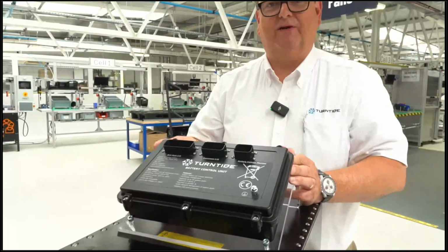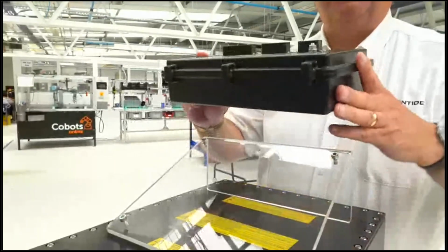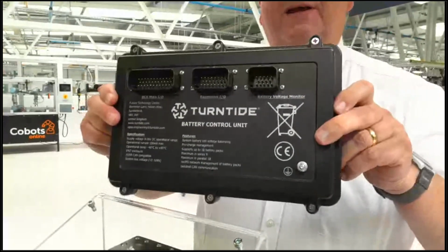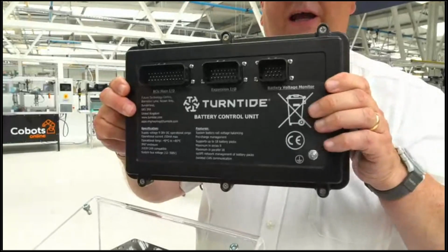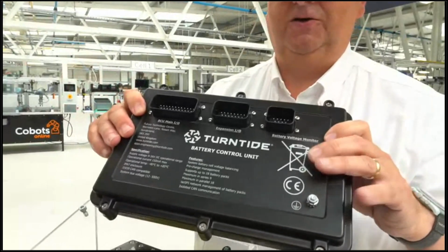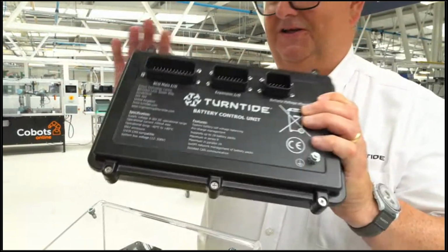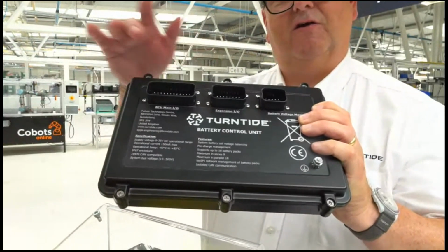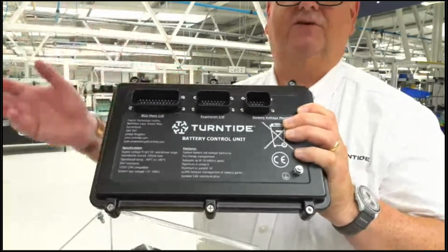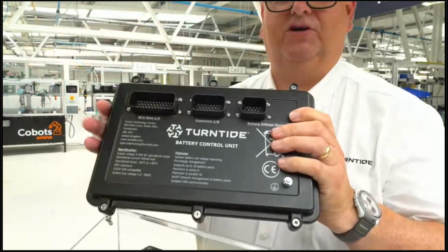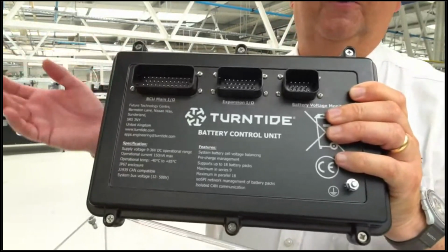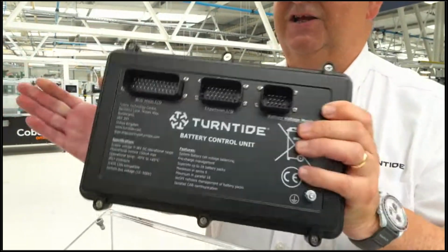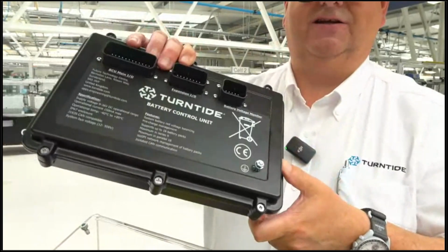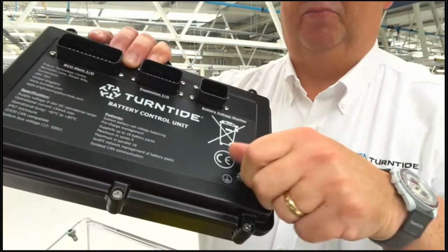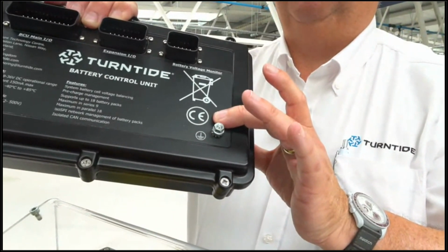I'll actually start with our battery control unit. This is like the master battery management system. We hook up the individual energy storage modules to what we call the BCU. There are various inputs and outputs - one daisy chains all of the packs together, and the other allows multiple inputs and outputs to a vehicle controller. We can control contactors for pre-charge and for switching on thermal management or cooling systems if that's required. It's a very simple EMC-proof box, metal housing, standard box, 3 connectors, pretty much plug and play. We also have an earthing point on this, and importantly, CE marking.